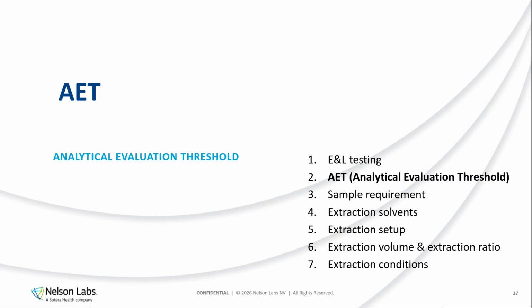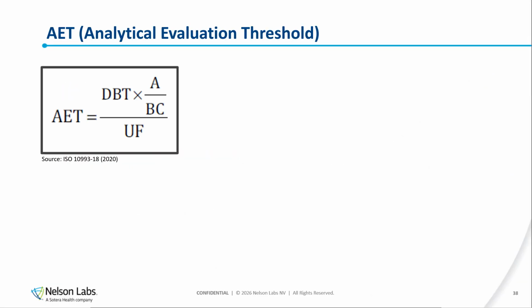So now to the AET, or the analytical evaluation thresholds. I will try to not go too much into detail, but it is very important to understand what this is for the whole presentation, everything that follows after this. So in ISO 10993 part 18, there is a formula given that shows how to calculate the AET, and it's given on the screen here. The AET is a concept introduced for organic screening methods like GCMS or even LCMS, which are very important part of an E&L study. And those will be used for trace analysis of organic compounds of varying chemical properties. And the AET is used to calculate the level, how low you need to look for these organic compounds, and is expressed in micrograms per milliliter. So if it's not clear at the moment right now, but I hope to clear this up in the next few slides to understand what and why this AET is.